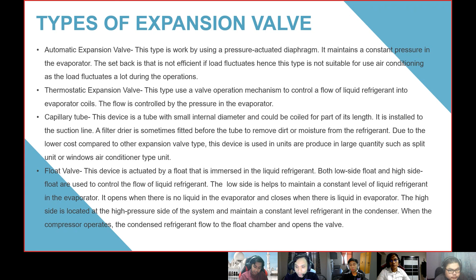The last type is the float valve. This device is actuated by a float that is immersed in the liquid refrigerant. Both low side float and high side float are used to control the flow of liquid refrigerant. The low side helps to maintain a constant level of liquid refrigerant in the evaporator. It opens when there is no liquid in the evaporator and closes when there is liquid in the evaporator. The high side is located at the high pressure side of the system and maintains a constant level of refrigerant in the condenser. When the compressor operates, the condensed refrigerant flows to the float chamber and opens the valve.